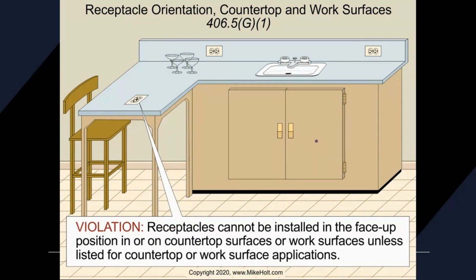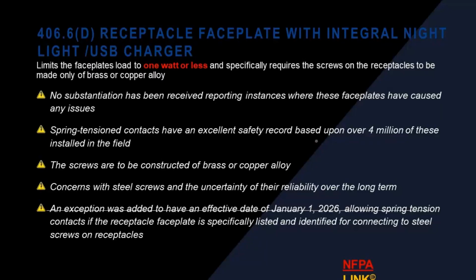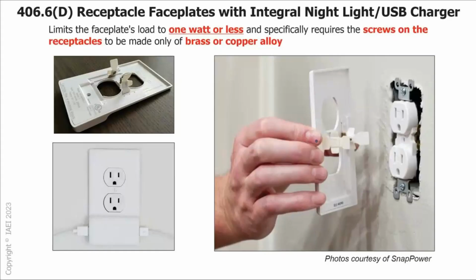Okay, 406.5(G)(1): receptacles cannot be installed in the face-up position in countertops. The new code again, and all these new ones you see with this 406.6 receptacle faceplate with integral night lights are now going to be acceptable inside the code. So this was a code change in 406 for this 2023 cycle. And this is an image of that. But you can only do it with a load that is 1 watt or less.